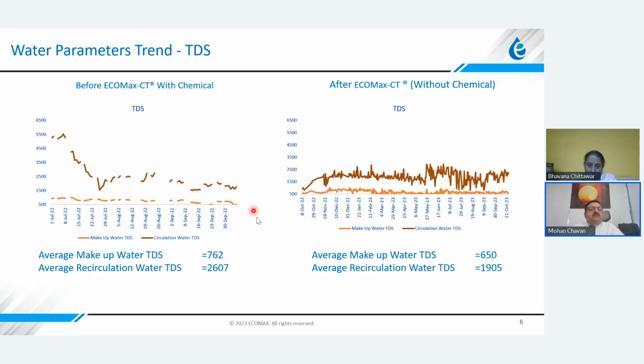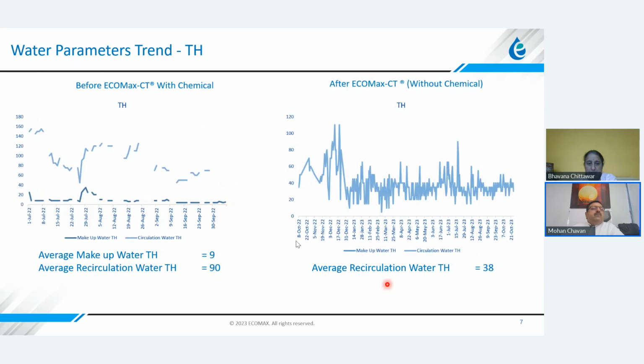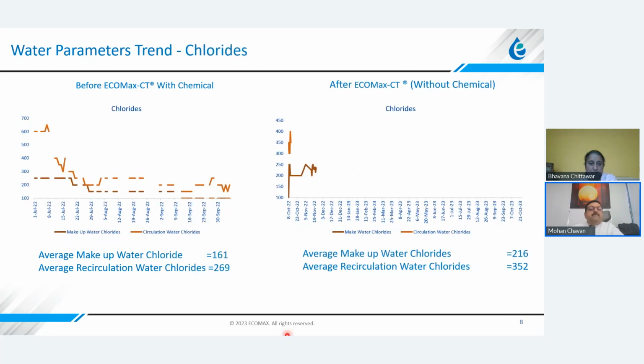Even the TDS, this is for circulation water TDS I'm talking about. Makeup was 762. Circulation was about 2600. And here, makeup was 650, and the system was able to maintain 1900 as the TDS. So 2600 to 1900. Same thing about TH. Earlier it was 90 in circulation water, now it's about 38. So you can see a clear improvement in the water parameters. Even the chlorides: makeup water chlorides were 161 and circulation water was 269. But here the makeup water chlorides were very high. In spite of that, the system was able to maintain it below 500, it is 352.